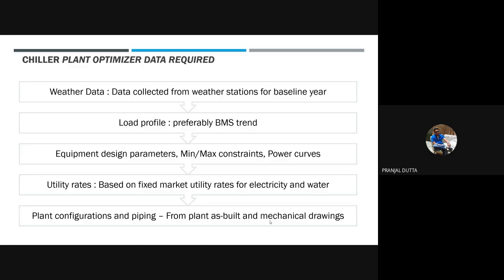Second, we need the BMS trend. Why is the BMS trend required? We need to know how the chillers performed over a particular year, because machine learning needs learning. So you should know how it operated in the last year. Based on that learning, it will take the next decisions based on the new data. So we need to provide some BMS trend on the chillers' load and their set points, and then all the operating data.